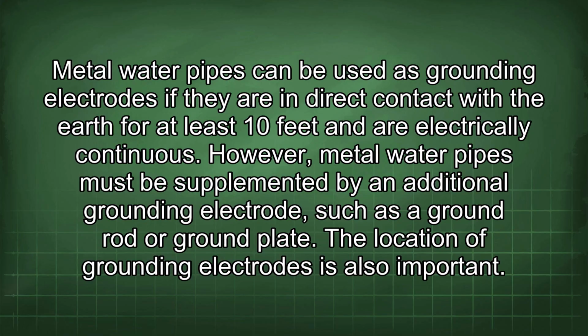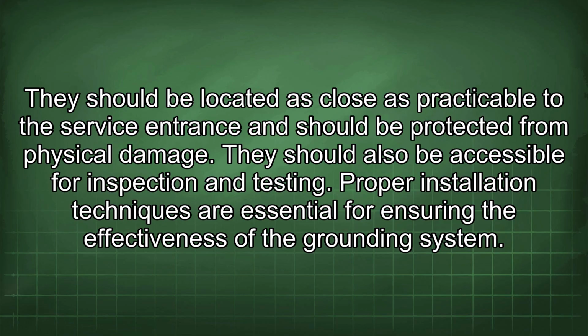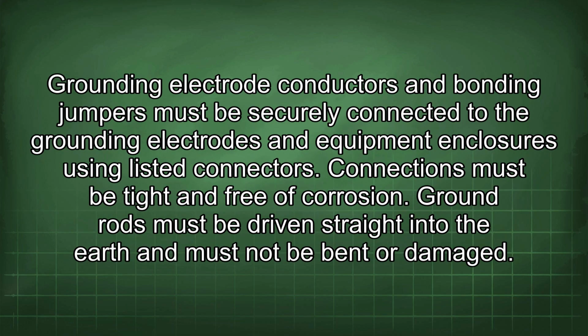The location of grounding electrodes is also important. They should be located as close as practicable to the service entrance and should be protected from physical damage. They should also be accessible for inspection and testing. Proper installation techniques are essential for ensuring the effectiveness of the grounding system. Grounding electrode conductors and bonding jumpers must be securely connected to the grounding electrodes and equipment enclosures using listed connectors. Connections must be tight and free of corrosion.